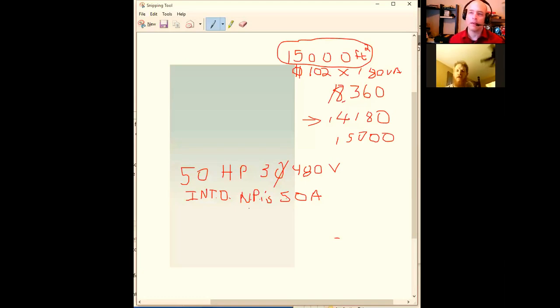Now you gave me an answer of the number 6. Is that right? Yeah. So had that not been, let's just say that question was just a regular motor that was not listed as intermittent duty. Even if they gave me a nameplate rating, in that case I'm going to ignore that and go back to the table value, and I'd pull 65 amps, I think is what it was. Yes. But I can't put that on the number 6 anyway, because I'm looking at 65 amps as a starting point. Then I have to take 125% against that number, according to 430.22, which is on the left-hand side of the page.